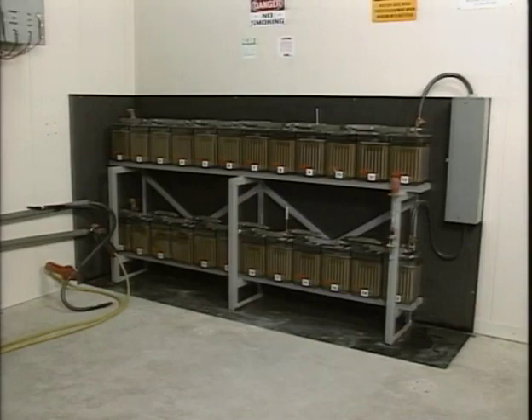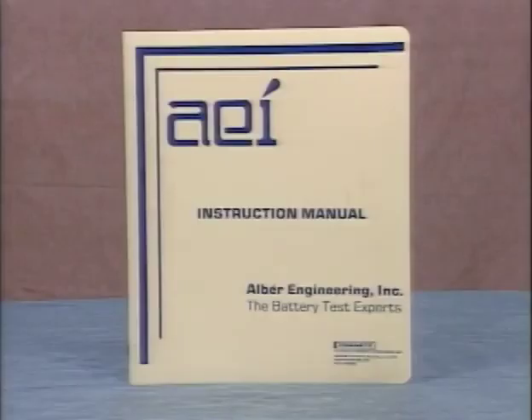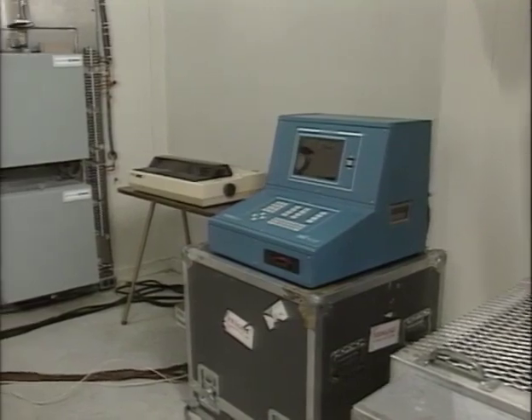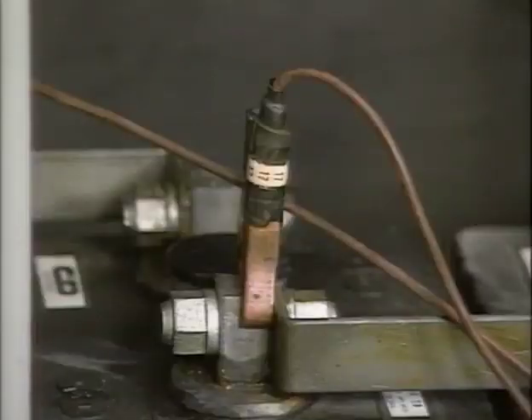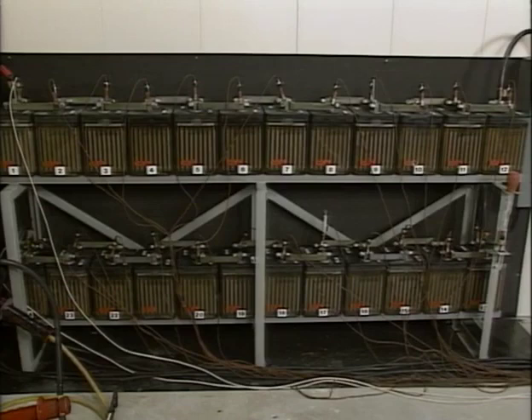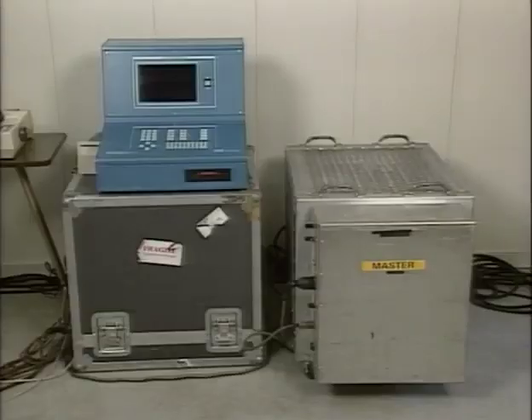Next, the test equipment will be connected to the station battery. Setup procedures vary with the equipment that's used. Be sure to follow the specific procedures for your test equipment. Here, test leads from a control unit were connected to the battery. A numbered test lead was placed in numerical order on each cell's positive terminal, starting with the first cell and continuing on to the last cell. With the leads connected in this manner, the control unit will measure the voltage drop for each cell and its intercell connector. Then the control unit was connected to a master load unit.